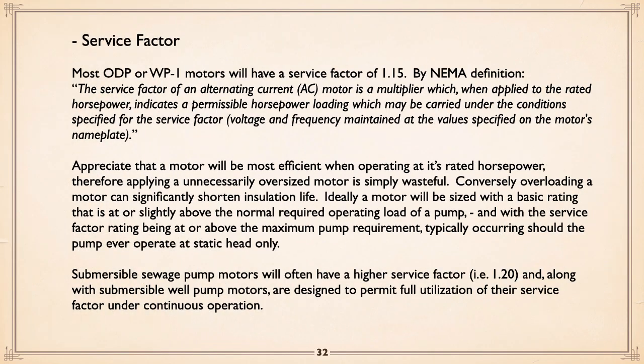Service factor. Most open drip proof or weather protected motors have a service factor of 1.15. And here's how NEMA actually defines service factor. The service factor of an alternating current AC motor is a multiplier which, when applied to the rated horsepower, indicates a permissible horsepower loading which may be carried under the conditions specified for the service factor. Voltage and frequency maintained at the values specified on the motor's nameplate. In other words, a little bit extra, but it is there.